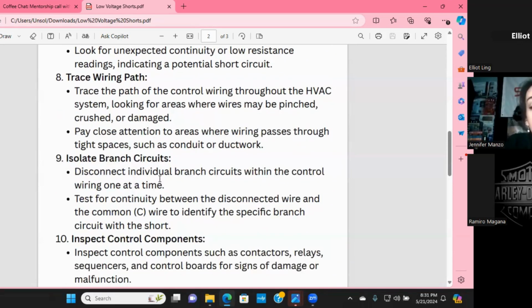You're going to trace the wiring path. You guys, I have had this happen to me before, and this is why I always put this here. I actually was chasing in an RTU. A lot of you know what an RTU looks like on the inside of the electrical panel. It's not a fun place to be. It's a very scary place to be. I thought I was chasing my 24 volt wire for my thermostat, and I was chasing a 24 volt that was factory installed. So I was testing continuity. I was getting continuity. I was ringing out just fine. The whole time, the problem was in the wire from the thermostat because I wasn't even actually testing it. I just thought I was. So chase your wires. Big thing.